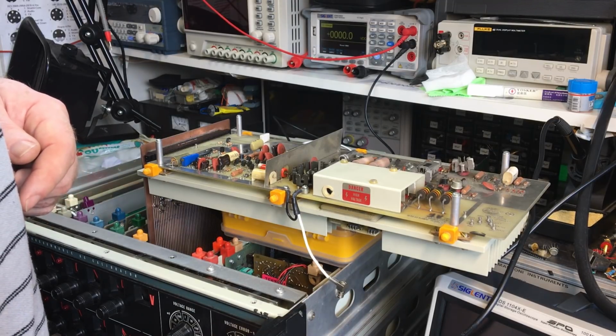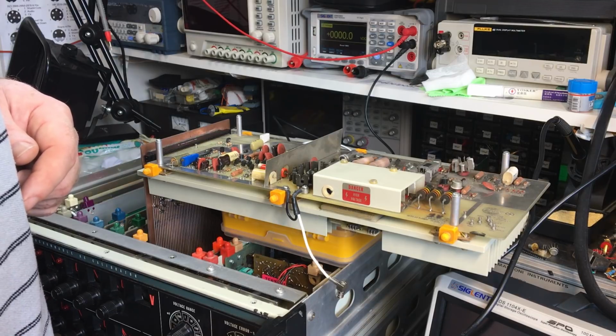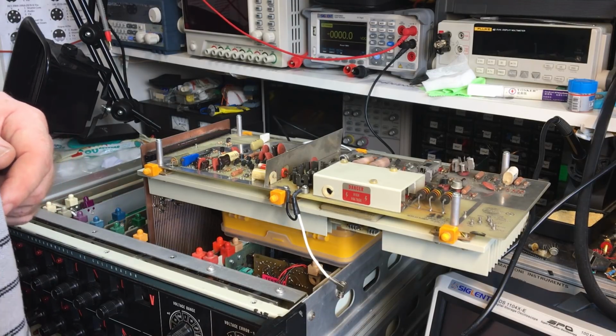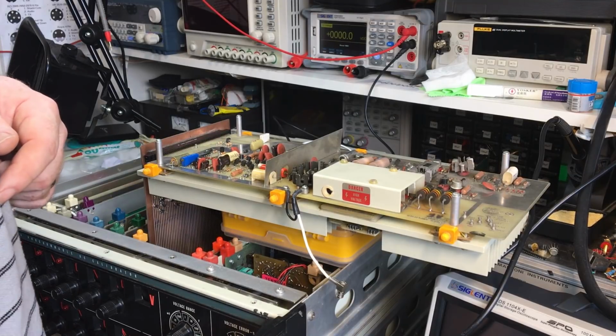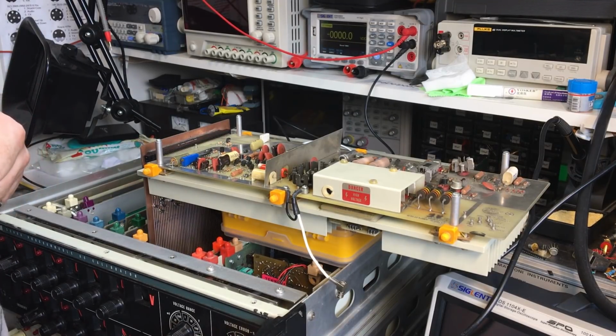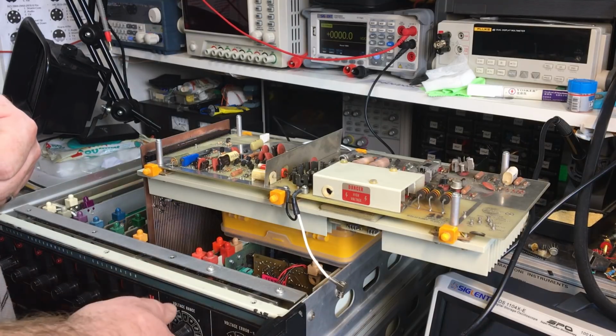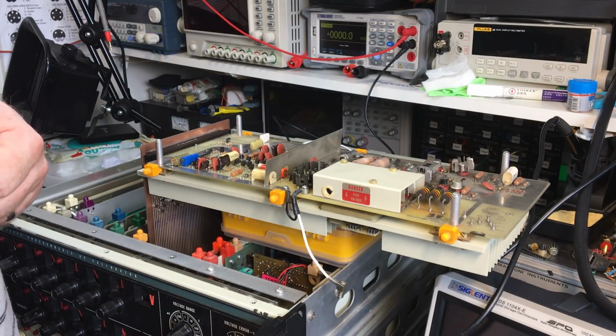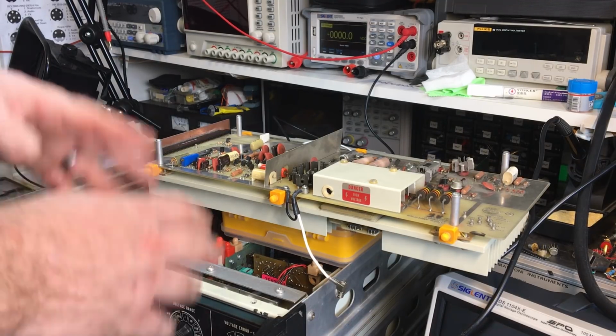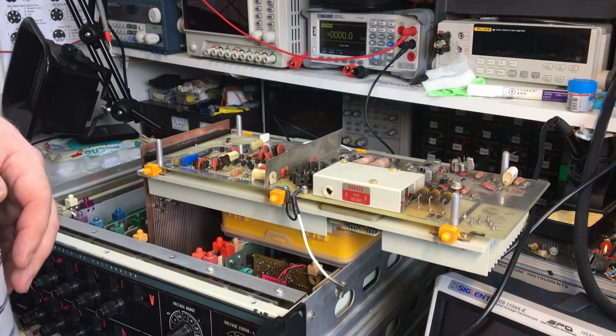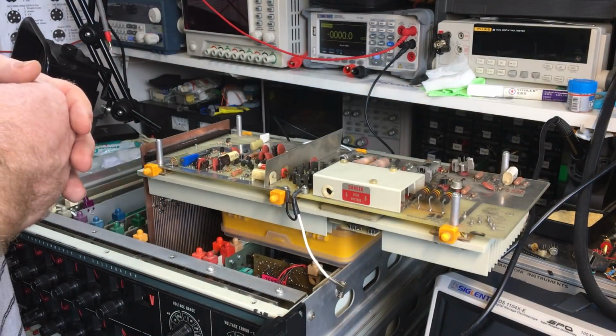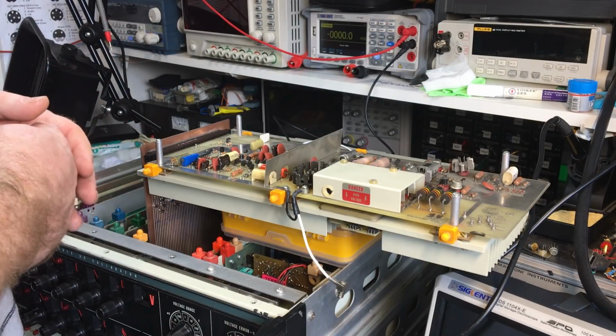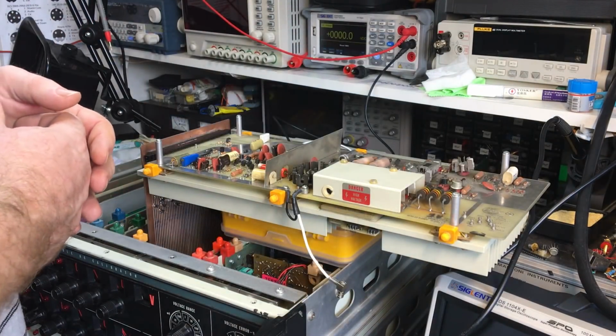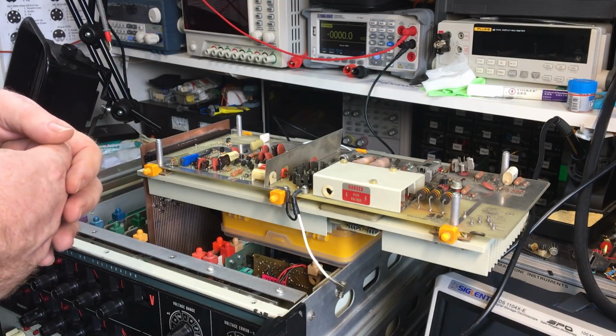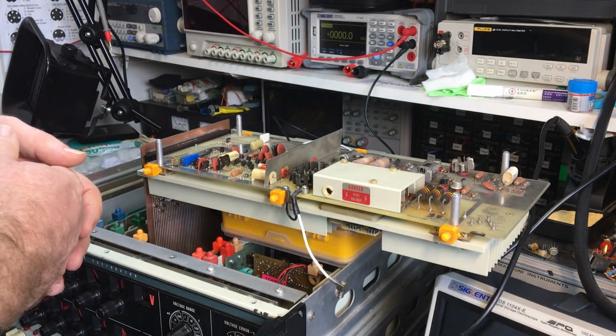So I haven't actually tested the bias. I probably should test for that first, even though I know normally I'm getting, I think it's about 27 volts DC. Is it negative 27 volts? Something like that, on those terminals at all modes. In a 100 volt mode I'm getting like minus 140 odd volts DC. So I know there's definitely a fault. So I'm inclined to just skip that step because I know it's wrong anyway. So I might just go through and test the voltages going into the card and work through the whole testing procedure, which is in the manual. That's the plan, and we'll see how we go with this.